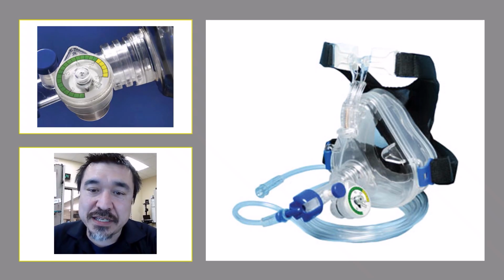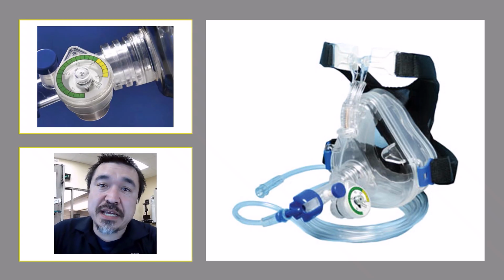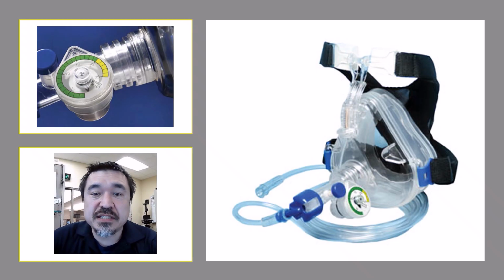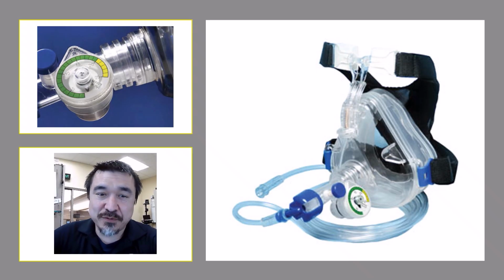Now there are limitations, of course. The max PEEP on this device is 13 as opposed to 15 on some others. They do admit that similarly to the Pulmodyne device, it can entrain more outside air when you have higher tidal volumes. So we need to be aware that as you increase PEEP and you realize that your FiO2 doesn't seem to be high enough, you can supplement this by a nasal cannula or by putting oxygen tubing right to the mask. This feature was important to the European EMS agencies. This might require a second oxygen source, but by the time you realize you need this, we should hopefully be at the ambulance.